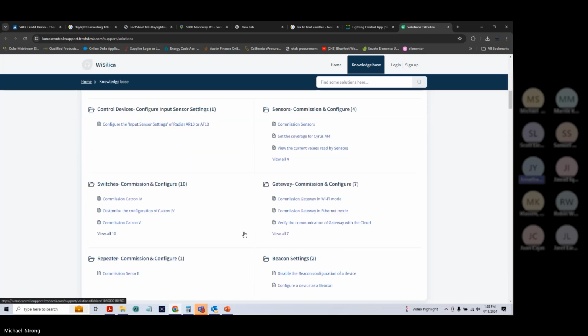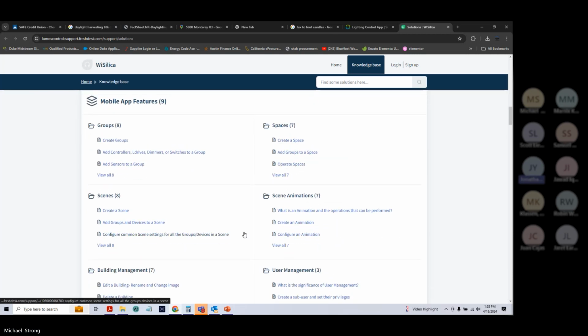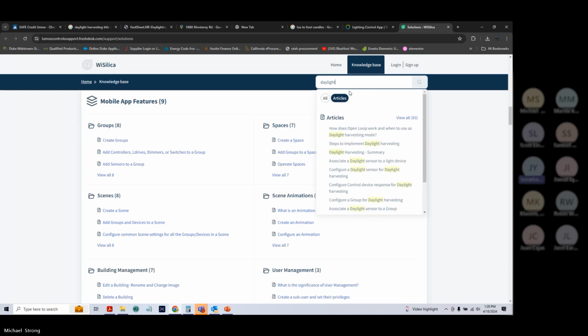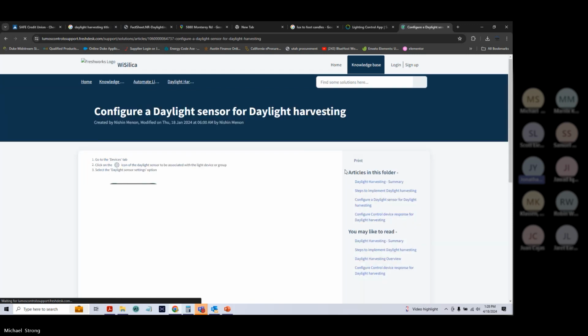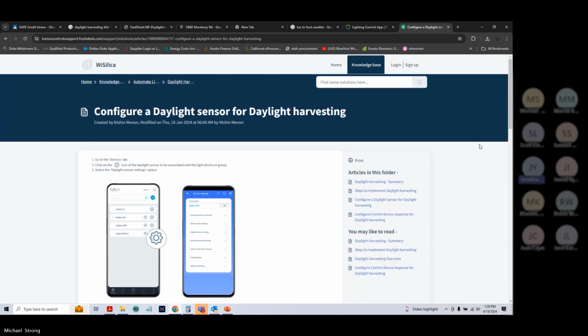When you add one of our controllers into a primary daylight zone, for instance, you can set the lux level that you want it to read in a closed or open loop setting. For an open loop setting, you'll be able to enter 2 lux values, 1 lux value when the lights are all the way on at 100%, another lux value when it's off at 0, and the light will change the intensity depending on how much lux level that sensor reads. It is a linear graph, so for instance, if the lux is right in the middle, the intensity will be at 50% for an open loop case.